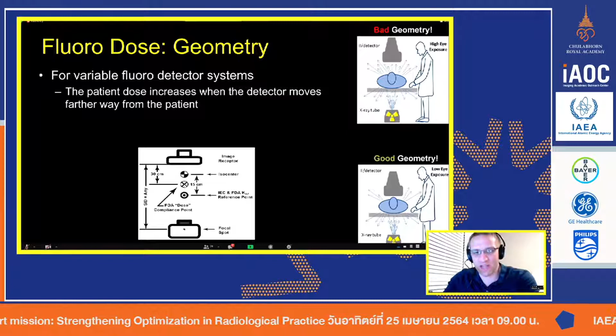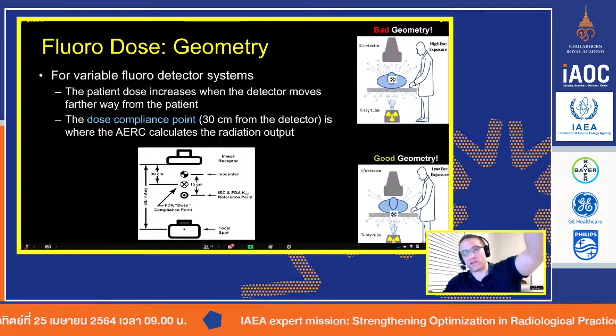So if this X is aligned with our international reference point, then the dose you see on the screen is going to represent the dose going into the patient, so the skin dose. Now, if you move your II or your flat panel away from the patient, you've moved that compliance point, that dose point, up. Now the skin dose is getting more dose because the system is trying to deliver the radiation output to this point. So let's say it was a good dose here. Now the dose is supposed to be quote unquote good right here. Therefore, everything below it is getting higher dose.